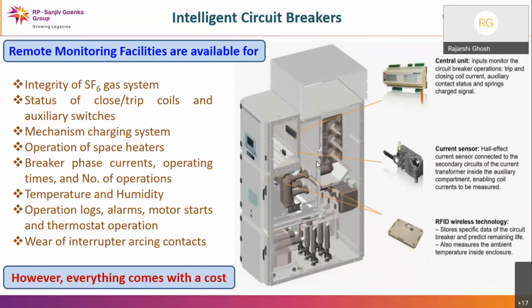So now the next part is intelligent circuit breakers. With modern switchgear, we can have the advantages of remote monitoring, which ultimately helps us to optimize our OPEX, that means the operational expenditure, to a great extent, and defer the capital expenditure investment by extending the asset life. Remote monitoring facilities are now already available for checking the integrity of the SF6 gas system, status of close and trip coils, mechanism, operation of space heaters, current, voltage, operating time, number of operations, temperature, humidity. All these things can be easily measured or sensed from the field itself, and communicated to the station or to the control room, where we can get all the requisite data for taking necessary actions.